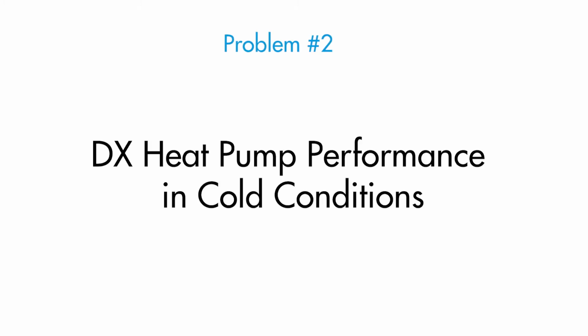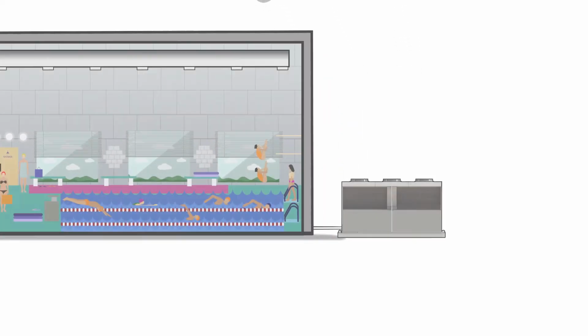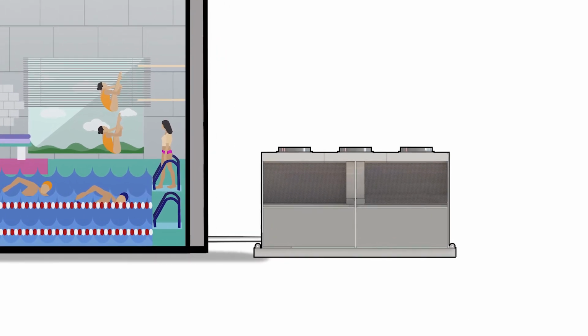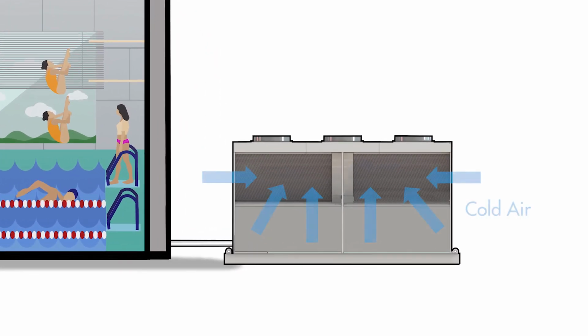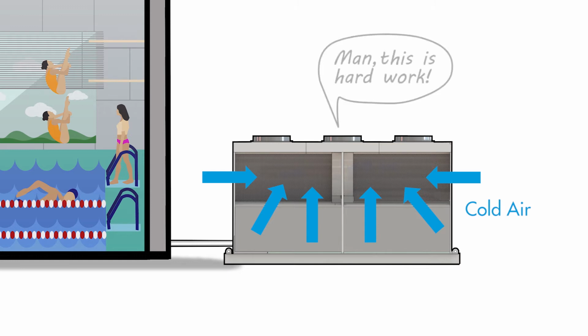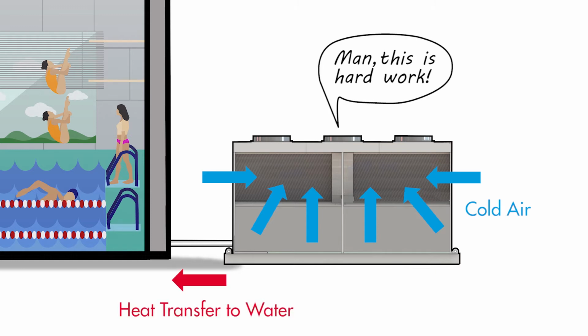Problem 2. DX heat pump performance in cold conditions. The performance and efficiency of DX heat pumps for either air or water heating can suffer in cold ambient conditions. When outdoor conditions are cold, a DX heat pump needs to work harder to absorb heat from the outside air and transfer it to either the air or water.